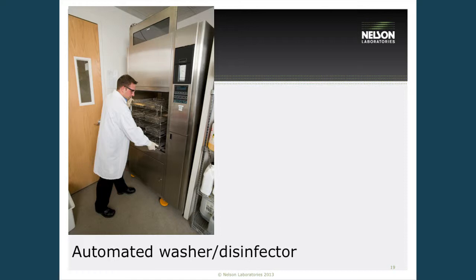So this is just a picture of an automated washer disinfector. One thing to keep in mind, like I said before, with standardized instructions is to make sure that whatever washer disinfector is being recommended for the type of cleaning procedure, that we are utilizing the standard cycles in that washer disinfector. We're not just choosing any type of soak and rinse, etc., because we all know that the central service personnel aren't going to put a specific cycle for each type of medical device that goes through. They're just loading it up to the fullest and running the cycle. So we need to make sure that those are standardized.